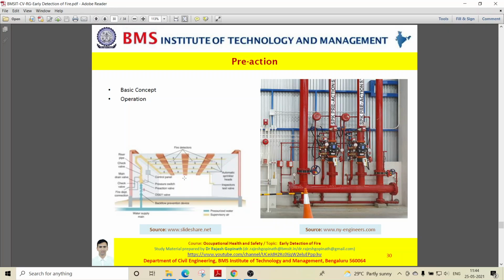In a very simple way, if I have to explain pre-action to you, remember, in a wet pipe system there is always water in the pipes. In a dry pipe system, it is pressurized air or nitrogen gas. In a pre-action system, you have to assume it's a system of dry pipes, that means it contains only air. I am not specifically saying pressurized air or nitrogen gas, it has air. But this dry pipe system becomes a wet pipe system because of an electrically operated valve. That remains the difference in your pre-action system. The biggest advantage of this system is its dual action, which is required for the water release.